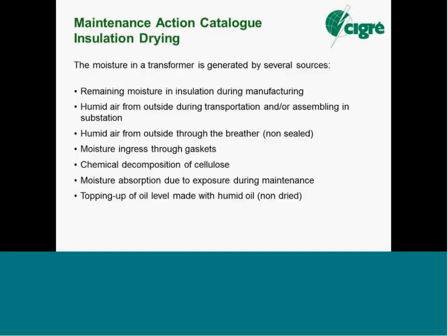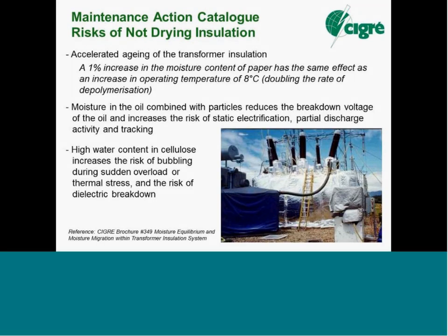Right, 5 minutes to go. I'm going to rush ahead just to get the most important points. What's left. Dry out, the typical site dryer setup in the photo there. Lagging to keep the transformer hot. Pump shrouded under that blue tarp, connected with a large bore vacuum hose and vacuum valve attached to the turret. So it's a field dry out being conducted because the transformer was of such likely high moisture content that it warranted a field dry out.